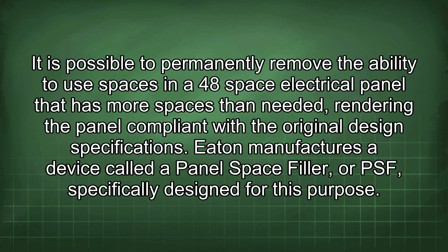It is possible to permanently remove the ability to use spaces in a 48-space electrical panel that has more spaces than needed, rendering the panel compliant with the original design specifications. Eaton manufactures a device called a Panel Space Filler, or PSF, specifically designed for this purpose. These fillers physically block the designated spaces, preventing the installation of circuit breakers. The process involves several steps to ensure both safety and compliance.